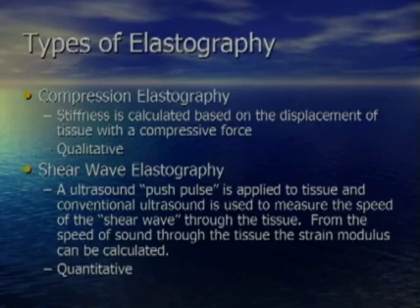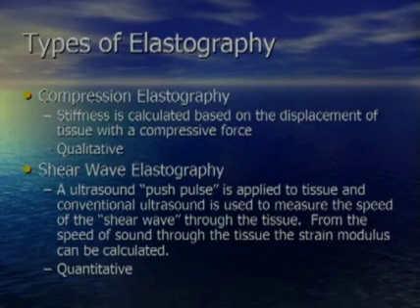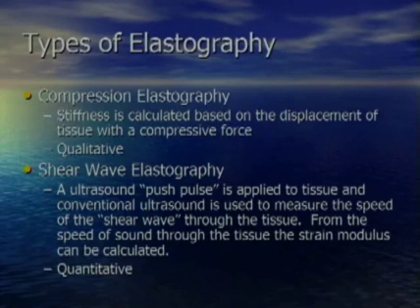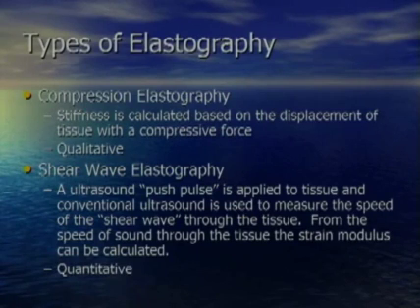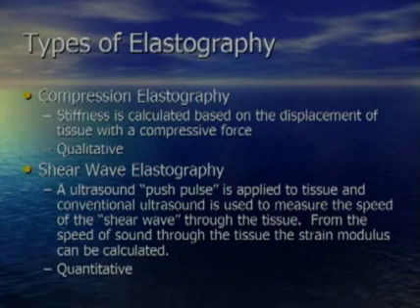There are two types of elastography. The first is compression elastography, where the stiffness of a tissue is calculated based on the displacement of the tissue with a compressive force. We apply pressure on the tissues, see how they move, and use ultrasound to determine if they're hard or soft. This technique is qualitative — it tells us how stiff something is relative to the other objects in the field of view.